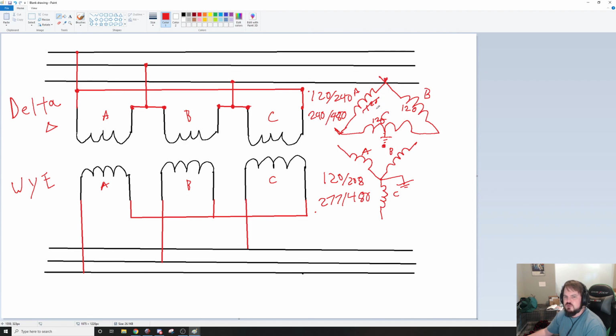Oh wait, no, these would be 240 volt coils. My bad. 240, 240, and 240. So if you read from here to here, it's 240. If you read from here to here, it's 240. If you read from here to the ground, or neutral, you'd get 120. And same if you read from here to the ground. But if you read all the way here, you're going to go through a 240 volt coil and a 120 volt coil, and you will not get anything useful.